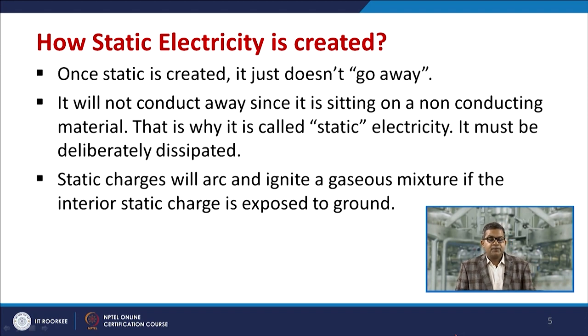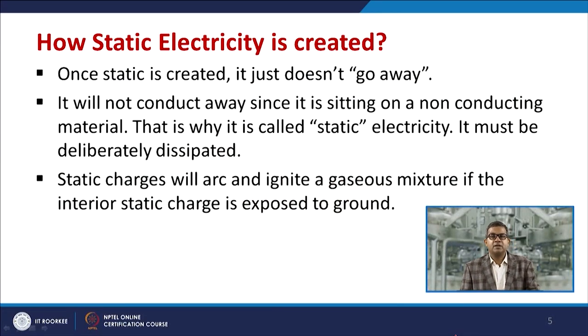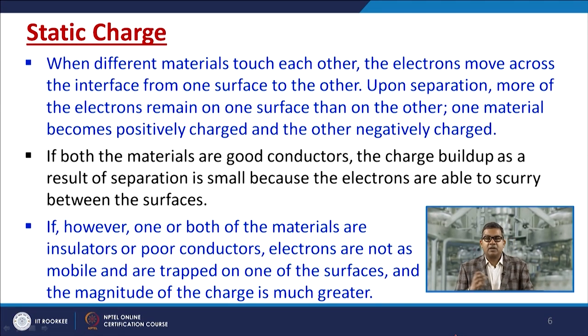Once static electricity or static charge is created, it does not go away. It will not conduct away since it is sitting on a non-conducting material — that is why it is called static. It must be deliberately dissipated with available tools, otherwise nature will do it on its own. Static charges will arc and ignite a gaseous mixture if the internal static charge is exposed to ground. These sparks or arcs may have sufficient energy to ignite flammable material, provided the concentration is within the LFL and UFL zone.